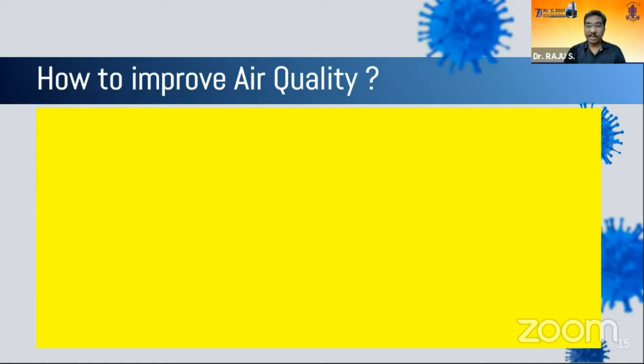So how can we improve the air quality? Some of the things that we can do is increase the ventilation rate, or what is called the air changes per hour. In mechanical systems, this has to be done and recalibrated by an AHU expert. We cannot meddle with that.